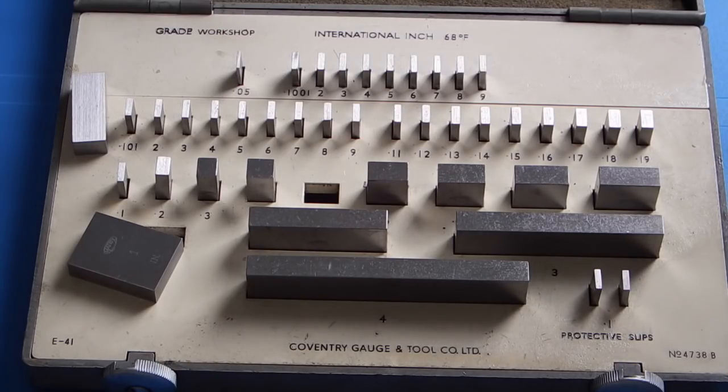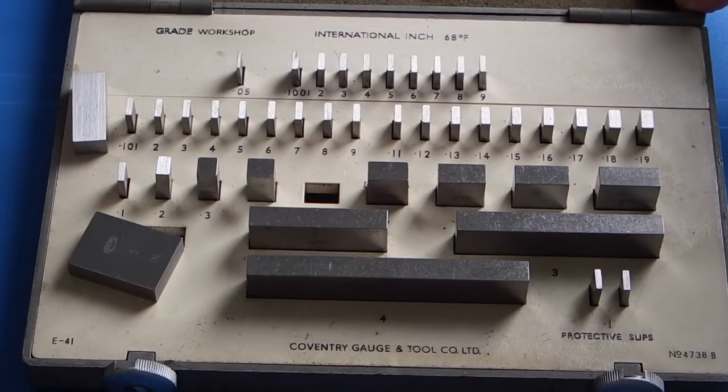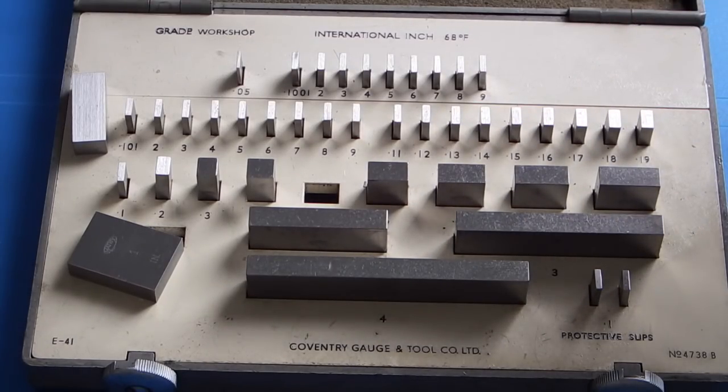Each set of blocks should have a calibration certificate showing the tested size of each block and the error of each block. Now I haven't got a certificate with these, and for me it's not worth paying to get a certificate because it would be quite expensive. I don't need a calibration certificate because I've not had any slip gauges up to now, and this is far better accuracy than what I've had in the past, so at least now I can check my micrometers.